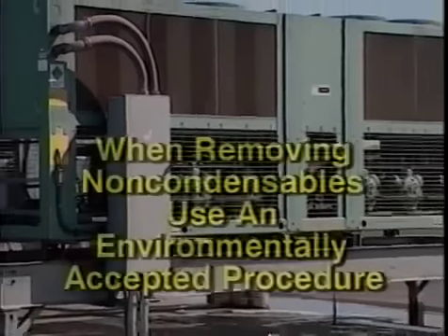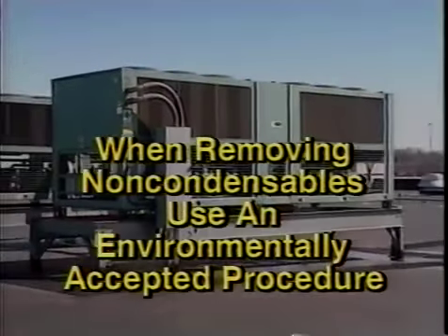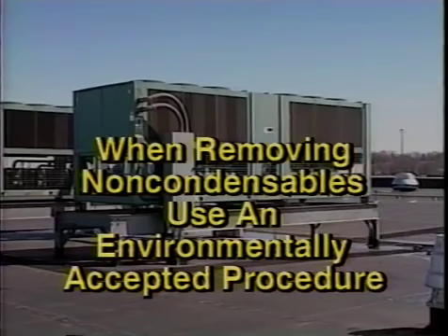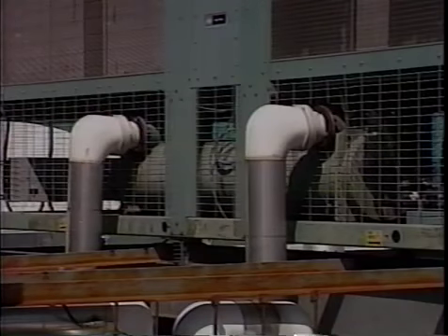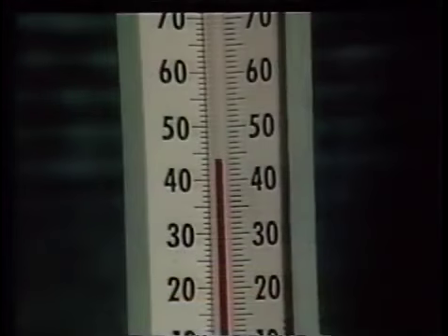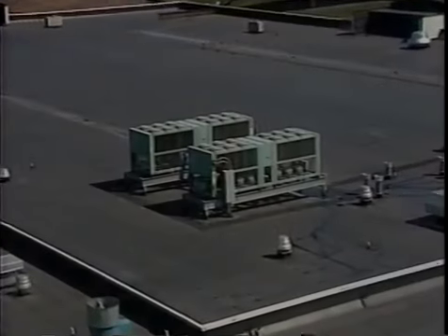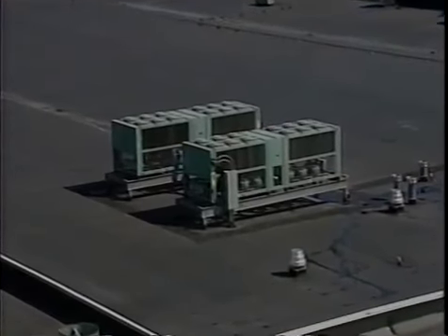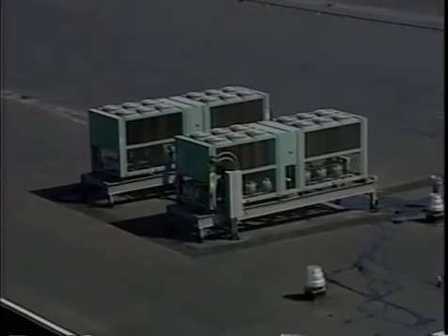To remove the non-condensables from the condenser, use an environmentally accepted procedure. Removing the non-condensables should quickly bring the condensing pressure down to a normal operating level. This in turn will bring all the other chiller operating data within design parameters. With the chiller capacity back to normal, the leaving chilled water temperature should drop to 44 degrees Fahrenheit, providing a 10-degree delta T for full system capacity. This will confirm the condenser was loaded with non-condensable gases, which probably entered the system during the last maintenance activity.